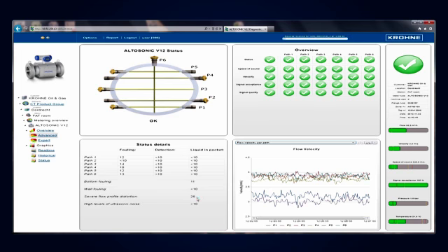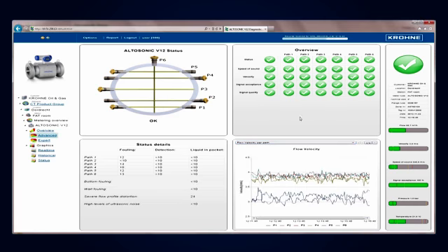You saw the setup, the meter is running atmospheric air, no inlet and outlet, so the flow profile isn't optimal. Once in a while it slightly goes up and we see a flow profile warning. Again, here you see the meter at this moment is running okay. Last thing you see on this page is the graph here. It shows velocity per path, but we could change this again by a click of the mouse into anything we would like to see. The lights you see here are basically a summary of the expert screen.